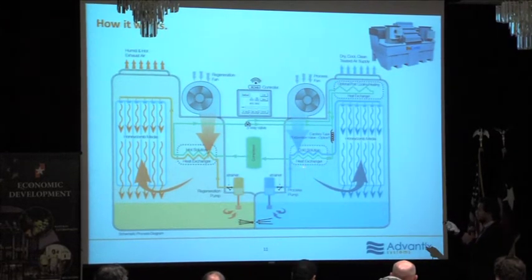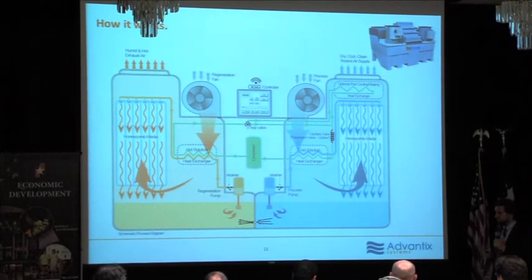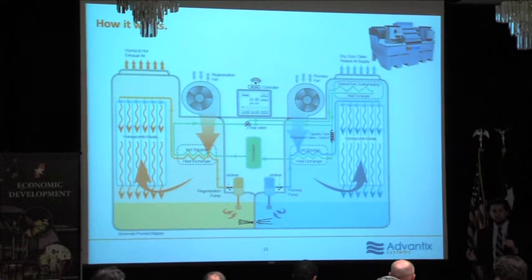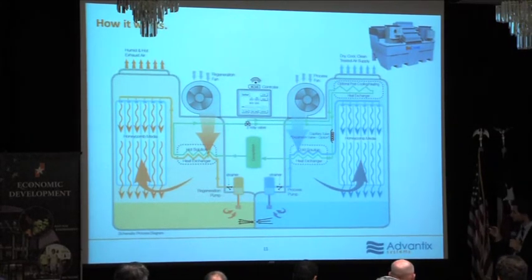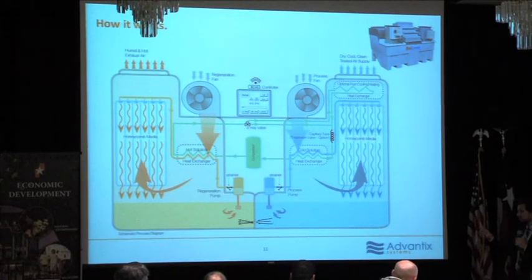So this is a proprietary part, a heat exchanger that we developed over the course of years, which is a shell and tube heat exchanger, copper on the inside, but epoxy-coated copper, and then the shell is going to be a reinforced polymer that goes around the shell part of that. A lot of the engineering went into how do you test those to make sure that coating didn't get scratched and cause a reaction that would eat away at the copper. So we have an impedance test that we perform at multiple times, and you can do this even in the field to make sure the coating is still integral on that heat exchanger.